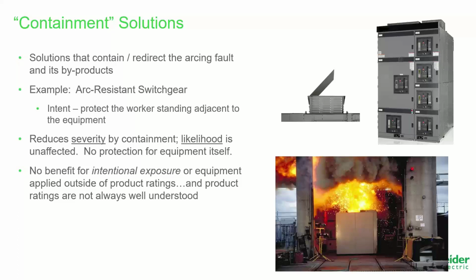Containment solutions, the last category, solutions that contain or redirect the arcing fault and its byproducts. And basically what we're talking about here is arc resistant switchgear. The intent is that the switchgear itself protects the worker who's standing adjacent to the equipment, reduces the severity, at least that the worker's exposed to. Likelihood is probably unaffected. It's like the reduction solutions. If you're racking a breaker in or out on this arc resistant gear, at least from what I understand about it, you're probably not any more or less likely to create an arcing fault. The benefit, though, is if it does happen, the gear is designed to contain that and to protect you.